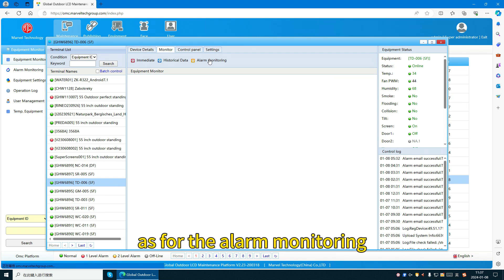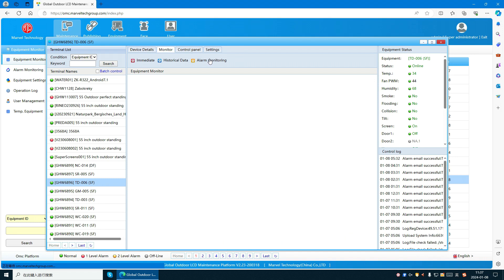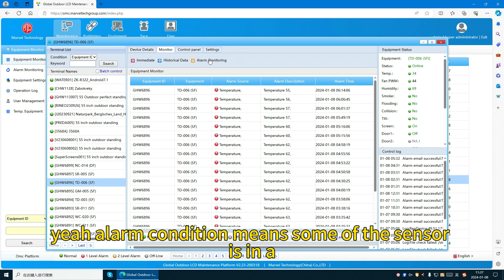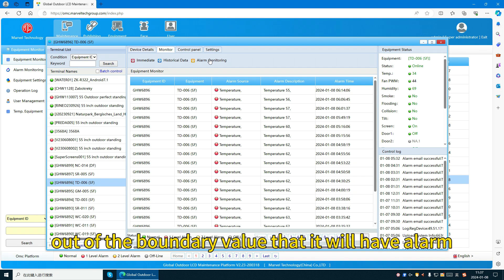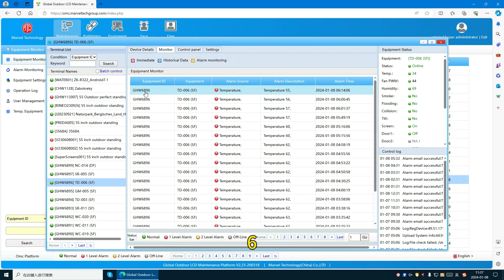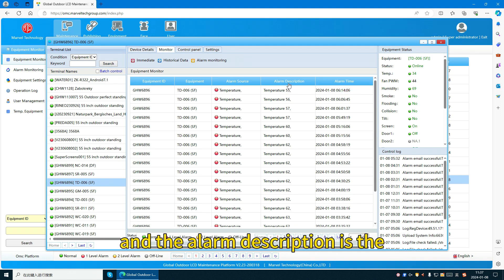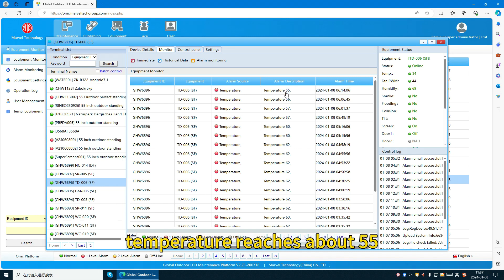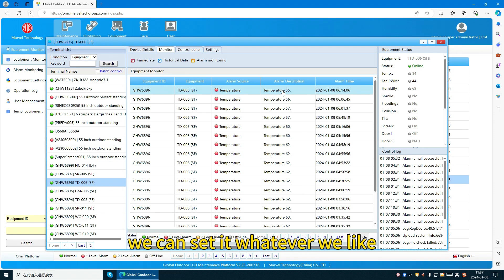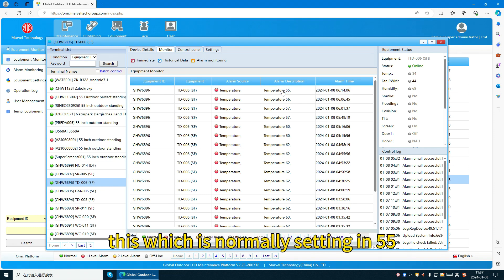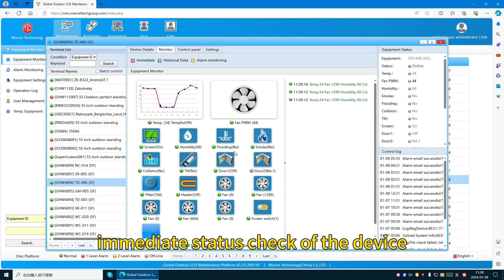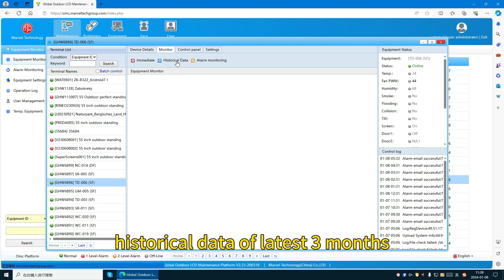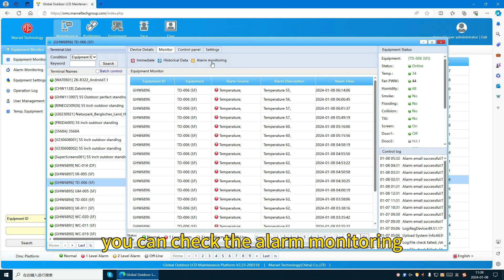For alarm monitoring — once the device is in an alarm condition, meaning some sensor is at or beyond the boundary value, it will trigger an alarm. For example, device 6896 has an alarm where the alarm source is temperature and the description shows the temperature reached about 55. The temperature boundary value can be set as you like, and is normally set at 55. In the monitor function, you will have an immediate status check of the device, historical data for the latest three months, and can check alarm monitoring directly.